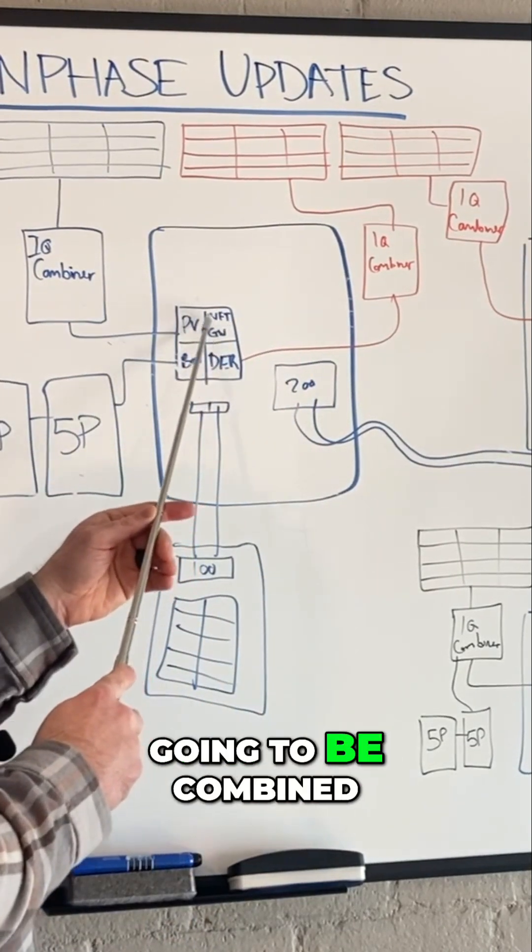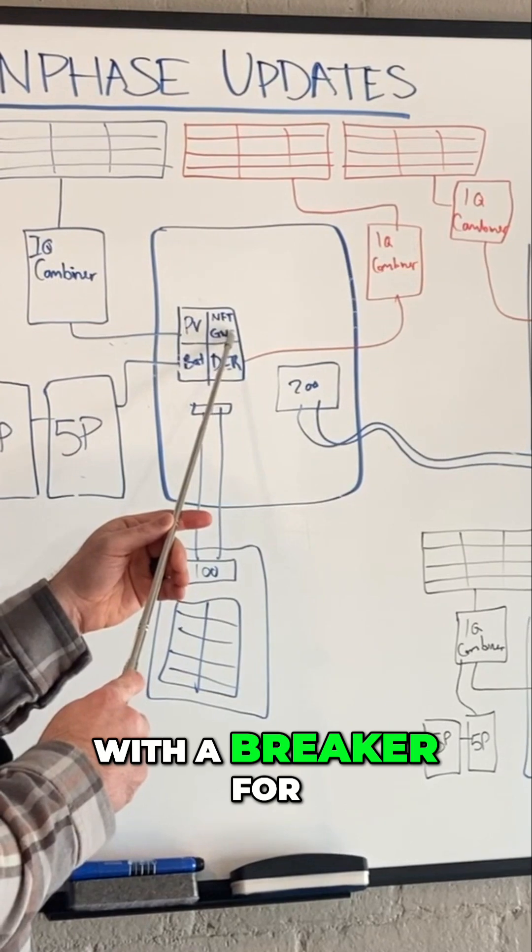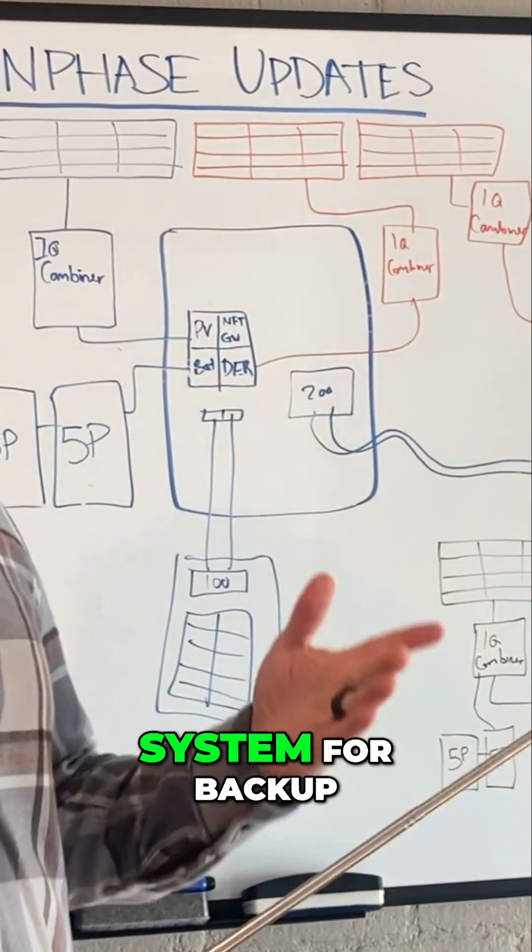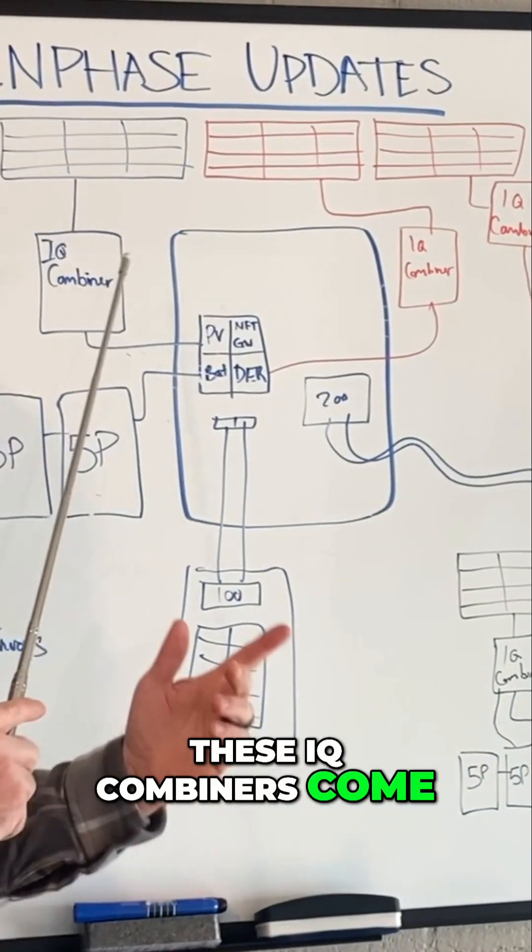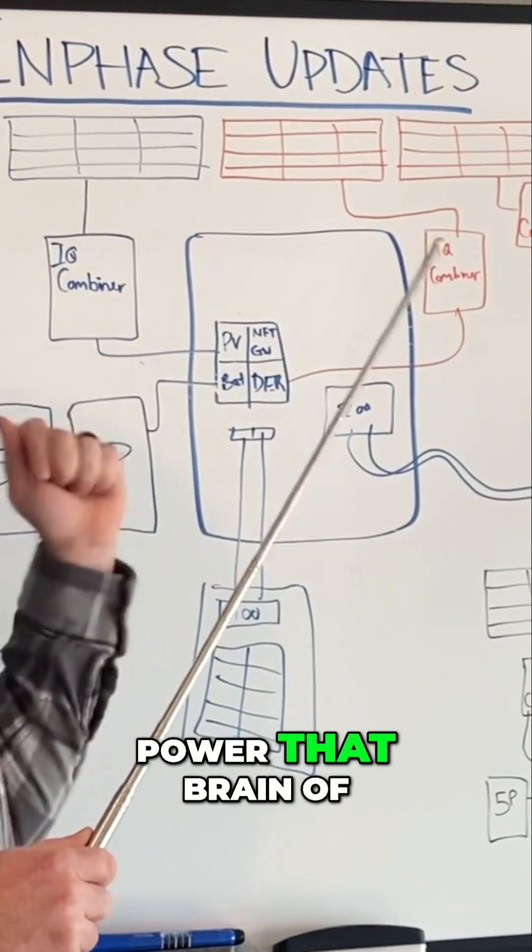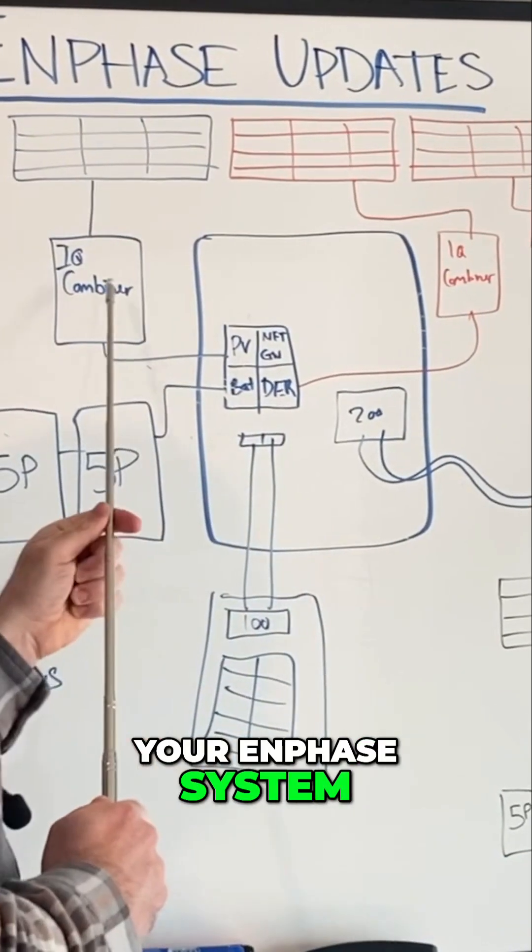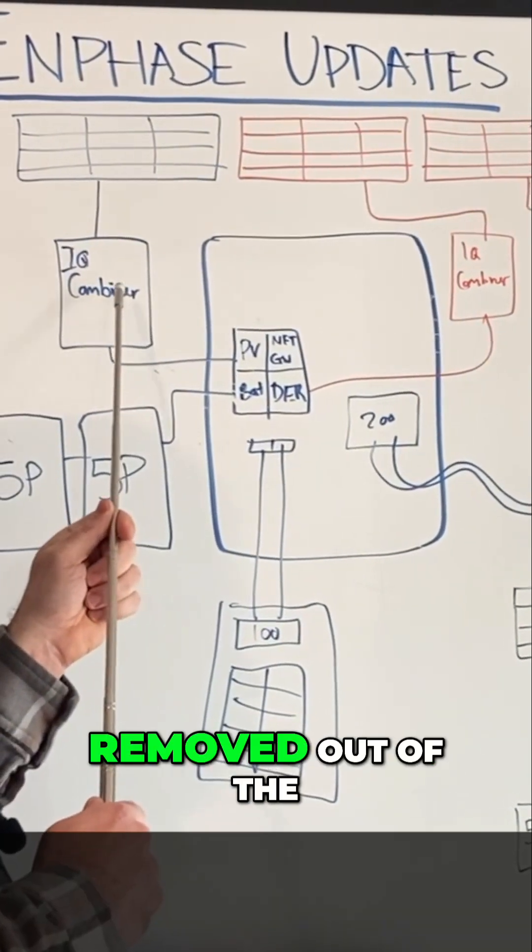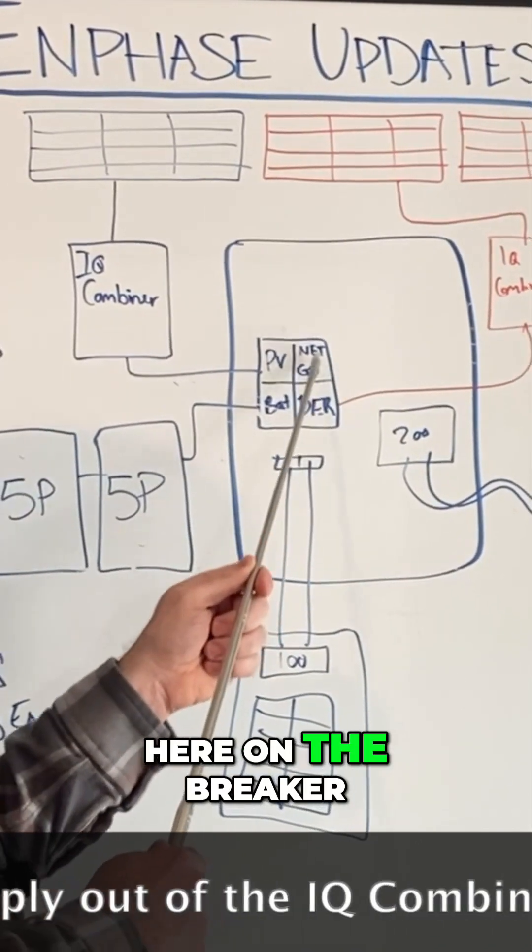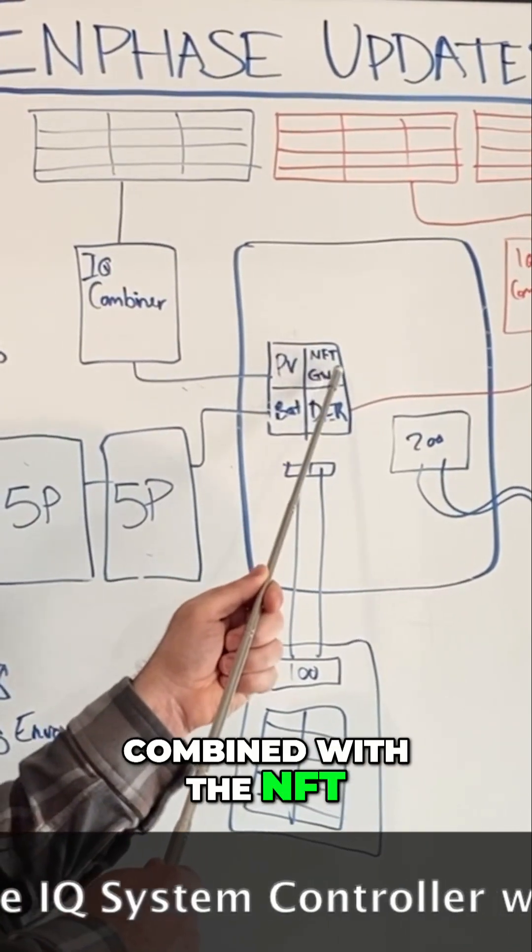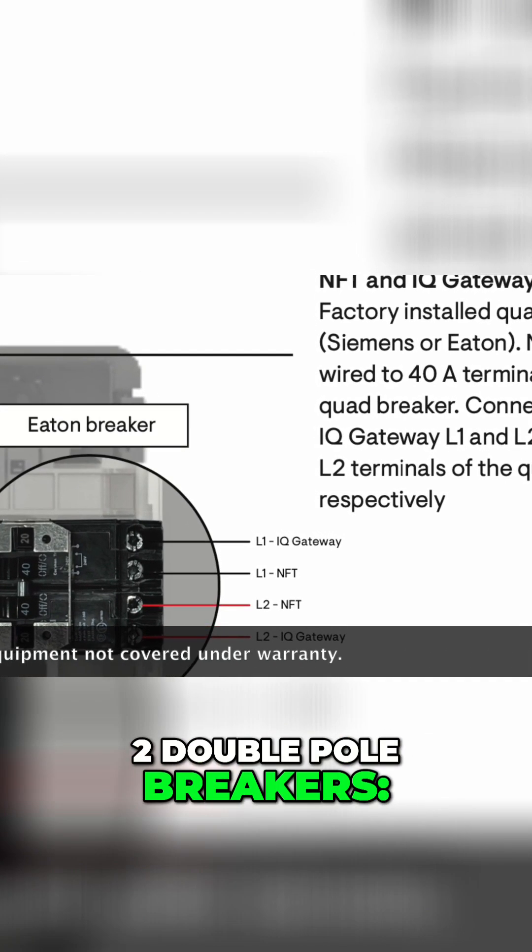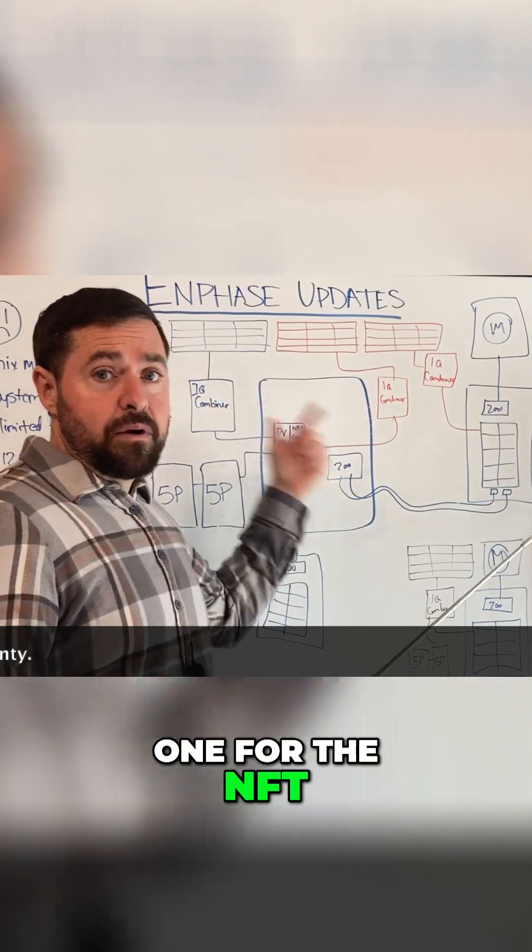That NFT breaker is going to be combined with a breaker for your IQ gateway, which is very important with an Enphase storage system for backup. These IQ combiners come built-in with an IQ gateway breaker to power the brain of your Enphase system. That has to be removed from the IQ combiner and terminated here on the breaker combined with the NFT. That's going to be a quadplex breaker, so it's kind of two double pole breakers—one for the NFT, one for the IQ gateway.